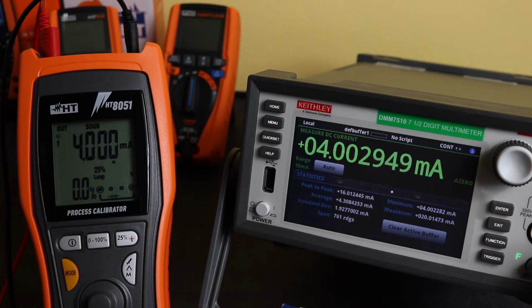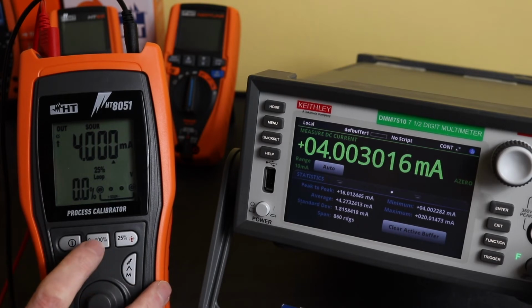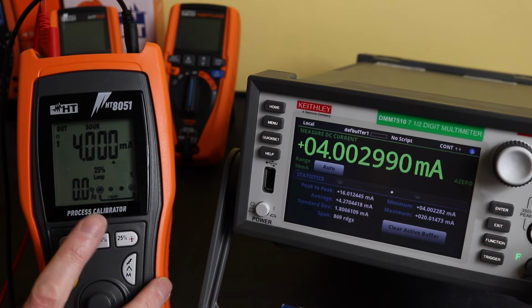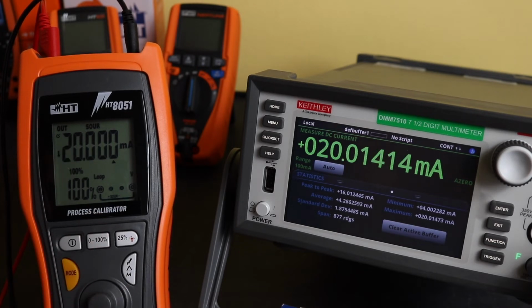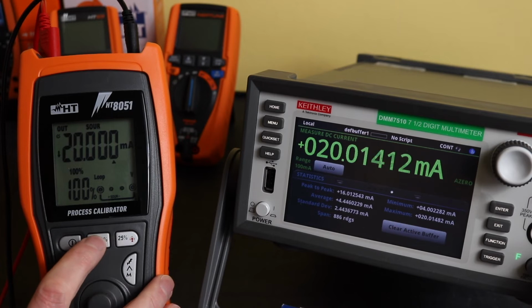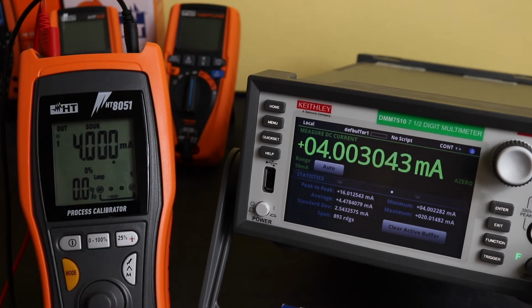Okay, so we've reconfigured and we've now set up to source milliamps out of the HT8051, and we just have the DMM in circuit here reading the current being generated at this moment in time. Once you've switched the meter from a measurement mode into a source mode, these other 3 buttons that you see here can now be utilised along with the rotary encoder just at the bottom of the picture here. The first button is 0 to 100%, just switches between the two. So we're on 0, which is 4 milliamp. I press it, it goes straight up to 20 milliamp, which is 100%. Press it again, it takes you back down to 0%.